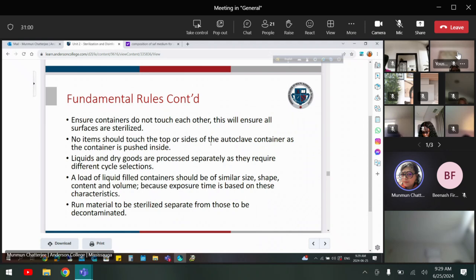A load of liquid-filled containers should be of similar size, shape, content, and volume, because exposure time is based on those characteristics. So in one cycle, you are not going to put a 1 liter flask with another 125 or 100 ml flask. If you put large volumes, put large volumes together, because it is time dependent. Large volume will take more time, and the smaller volume will take less time. And if you put extra time, it may cause problems.